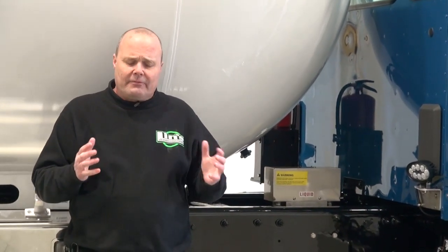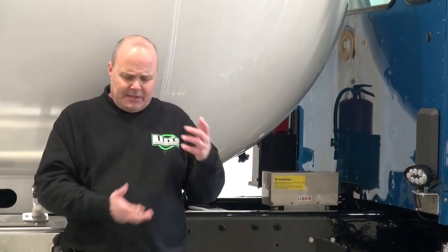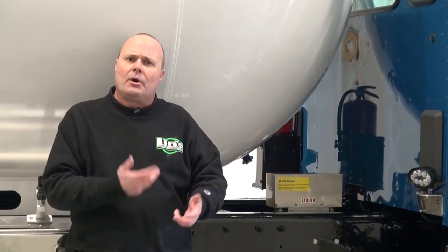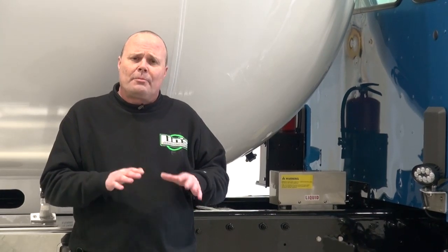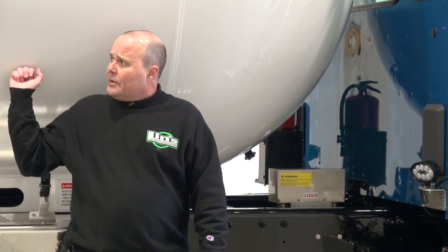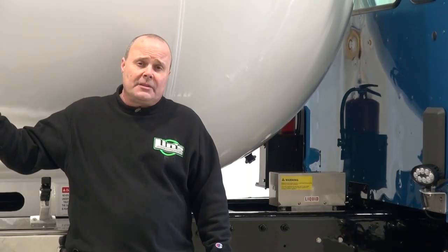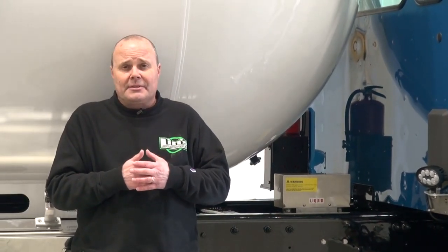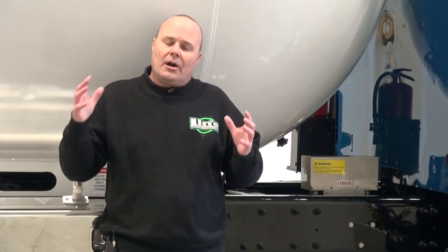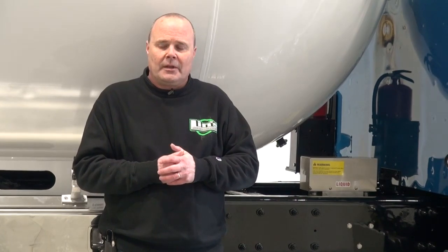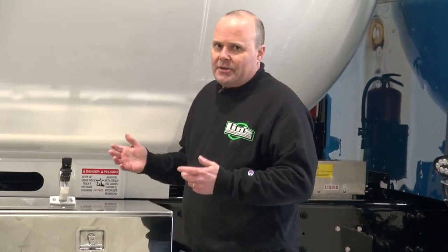Now we've all boiled a pot of water on the stove. We've seen those huge vapor bubbles coming up from the bottom as you get a rolling boil. Well, propane works the same way. As you start to pump liquid propane off this truck, it's dropping the pressure inside the tank and the liquid propane wants to boil. As it boils, all those bubbles are going into your pump. Now your pump is designed to pump liquid. So as you start to get that liquid along with all those vapor bubbles into the pump, it becomes much less efficient. So how does the heat exchanger help?